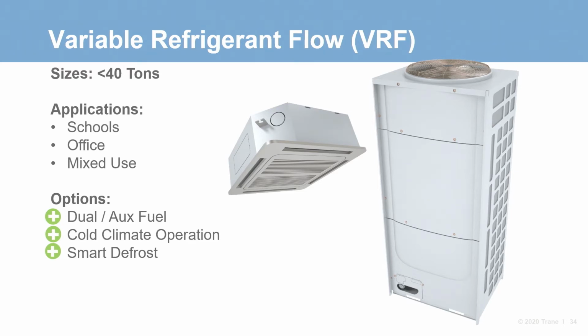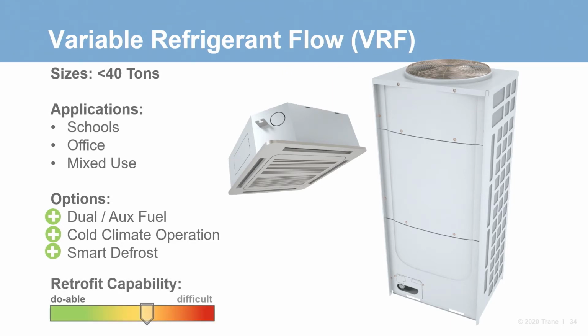There are a couple different ways this is accomplished by different manufacturers, but the end result is the unit goes through a defrost cycle, but some heat is still delivered to the zone to avoid occupant discomfort with cold supply air. VRF is an interesting retrofit opportunity, and the difficulty of that retrofit will be based on the existing system.